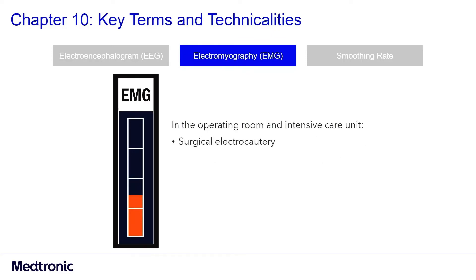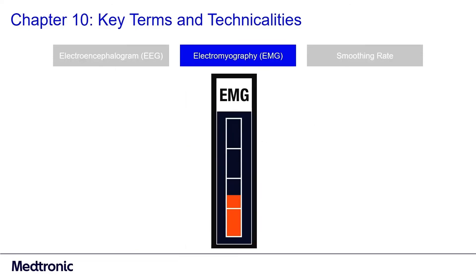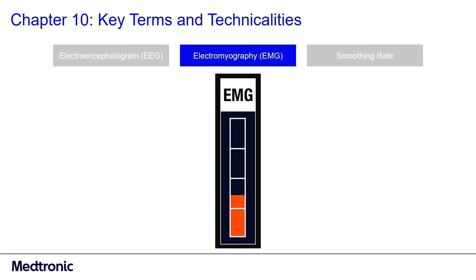Surgical electrocautery, ventilators, and electric warming blankets are examples of equipment and devices that can create high-frequency artifacts. When a high-frequency artifact is displayed, assess the source of the artifact and interpret the BIS monitoring value with caution.